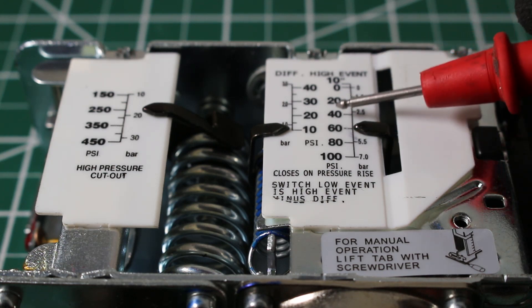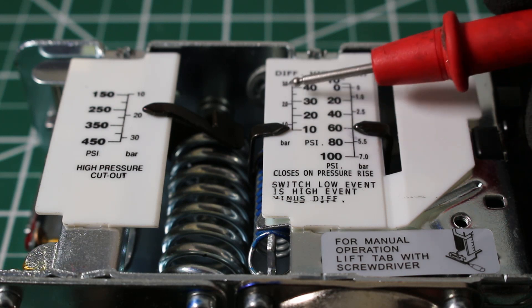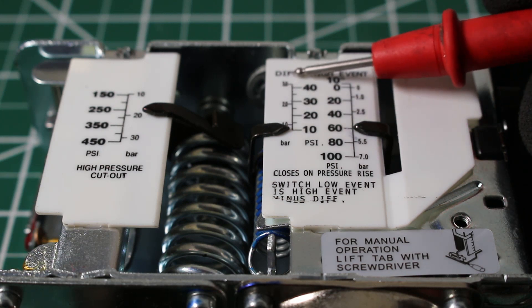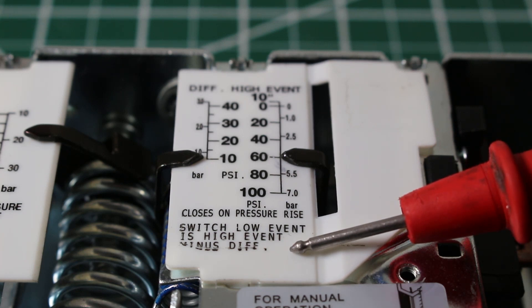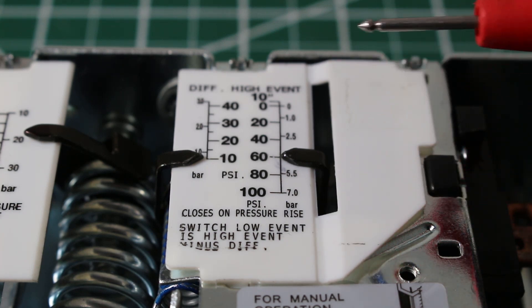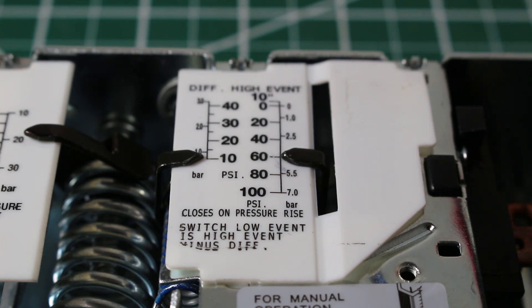The reason I said 50 is because this control right now is set to shut off at 50 psi and I will explain that. If we look at this tab, this is our differential. If we look at this tab, this is our high event. Let's get a clear image of that. Differential, high event. Here it states switch low event is high event minus differential. Sounds confusing, but it's really not. When you first learn about something, of course it can be difficult, but with a little bit of patience and time, you can achieve anything. So let's go over this.